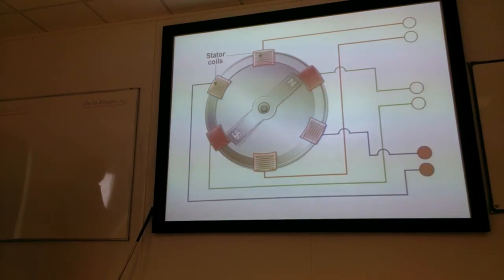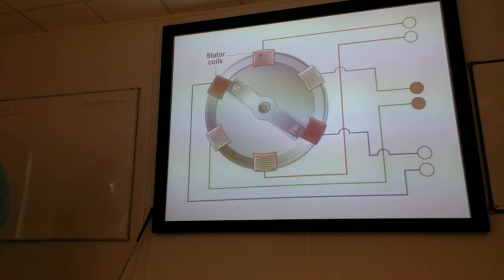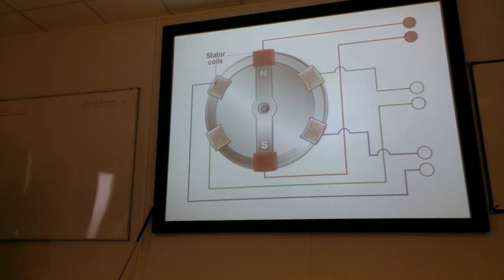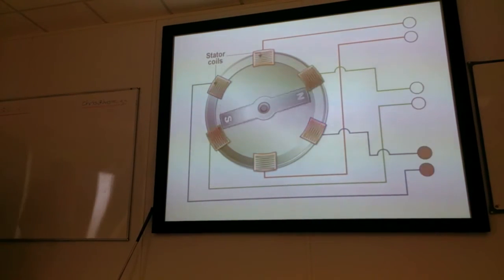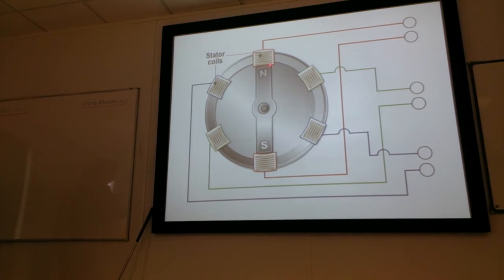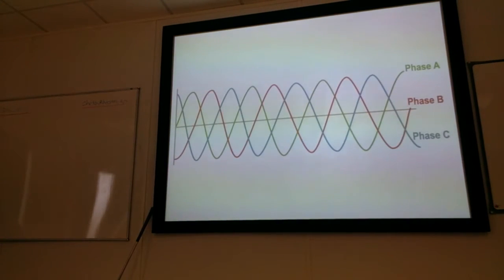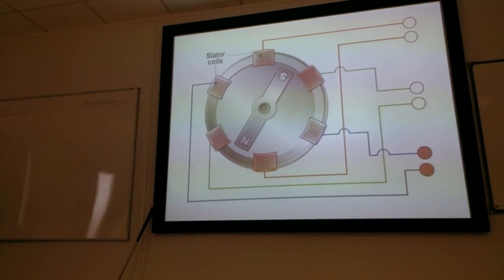Remember, it doesn't matter whether we turn a magnet inside the coil, or we turn a coil around a magnet, inside a magnet, or indeed with windings of electromagnets inside another bunch of windings. In this case, every time it goes past the pole, it's generating a pulse of AC electricity. If we were then to look at the AC electricity on an oscilloscope, we'd see that the three phases come out like that. And basically on those coils, each of those is connected.